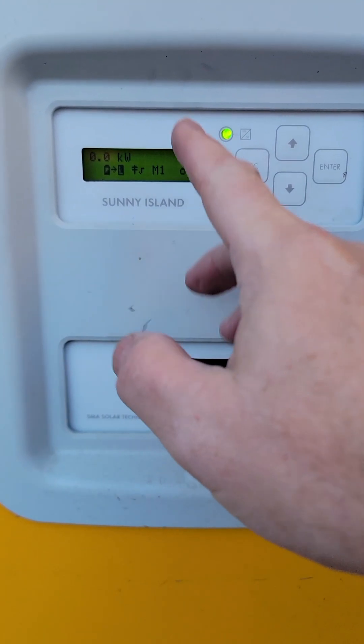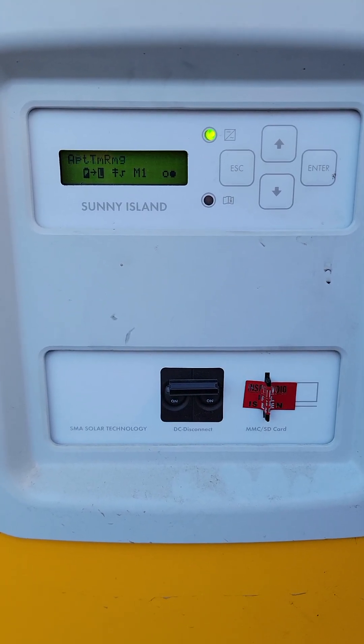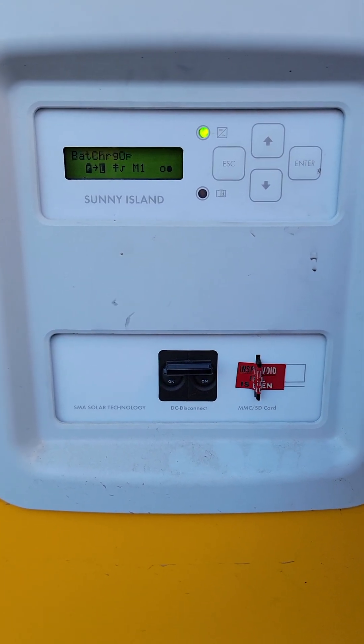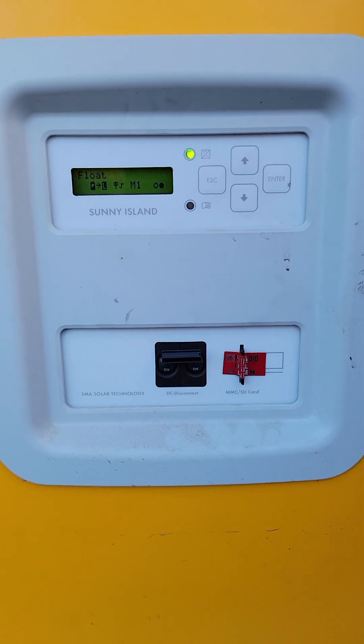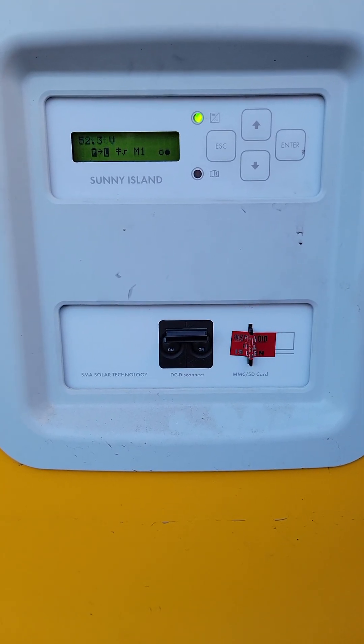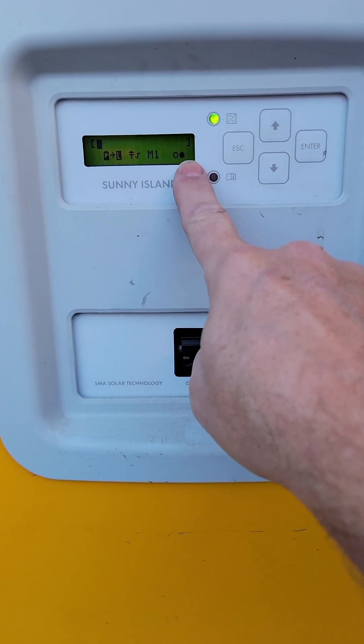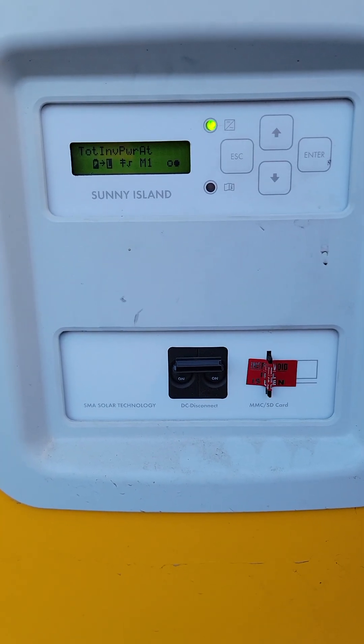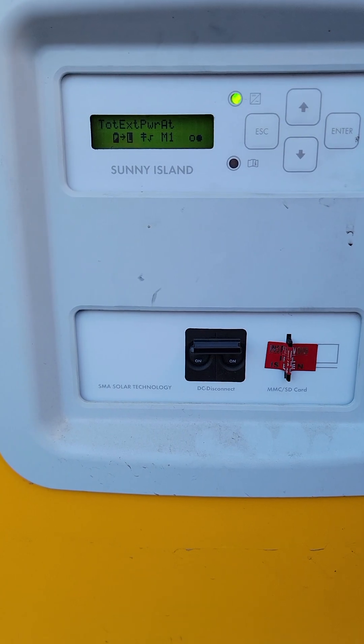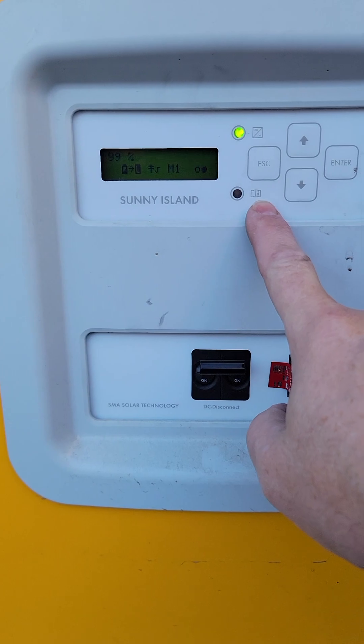What that says is: I basically had an unexpected interruption of power. If you get too many of those, the inverter can go into a safe mode where it says, let's not try to tell the generator to start anymore. That can be a reason why it wouldn't start. Other errors in there could be generator timed out or generator power failure — there's a whole bunch of different errors that can occur. But generally, if you don't see that exclamation mark flashing, then you're good.